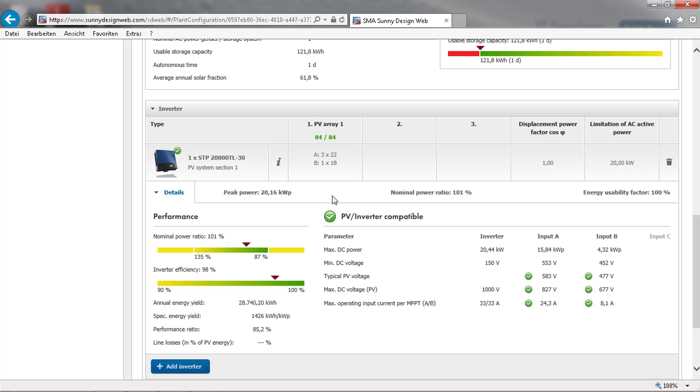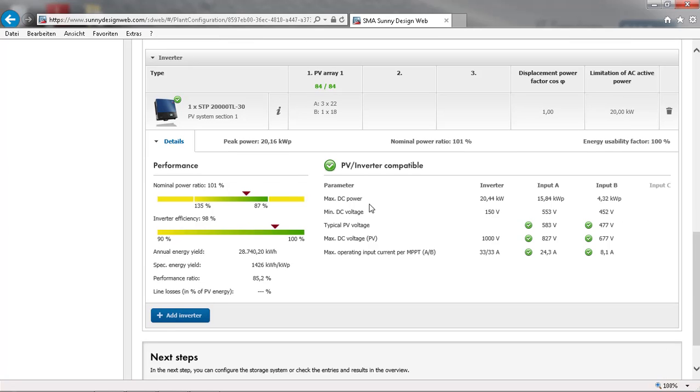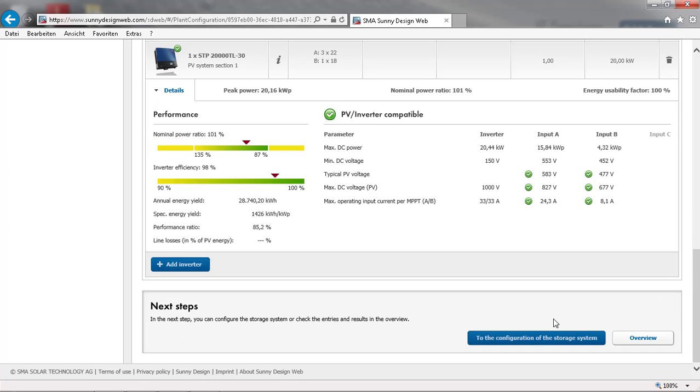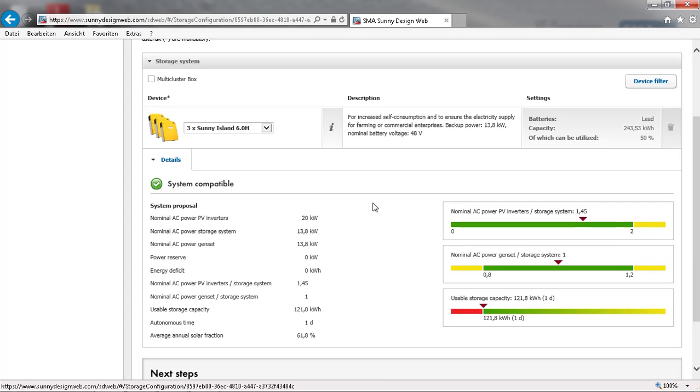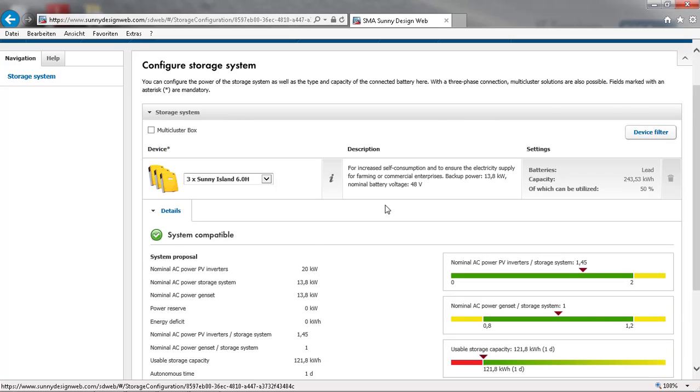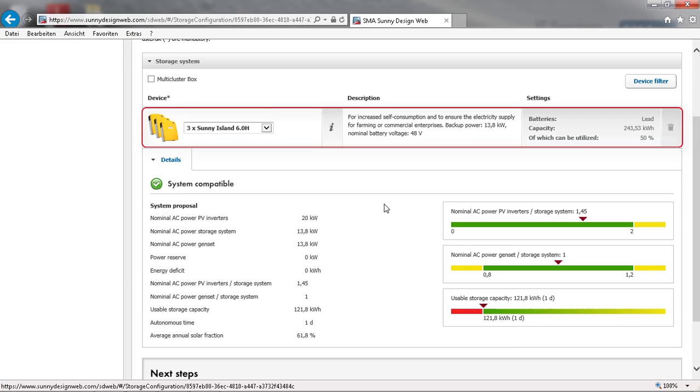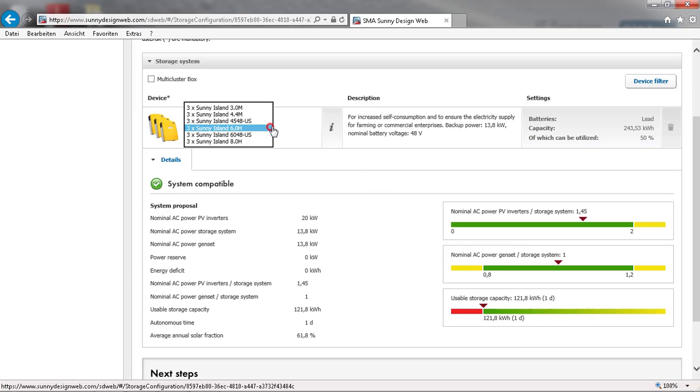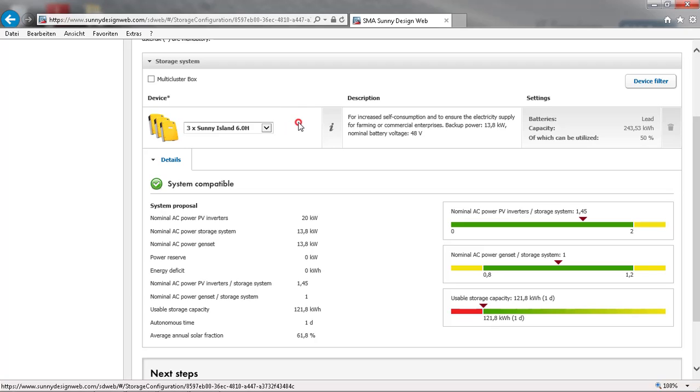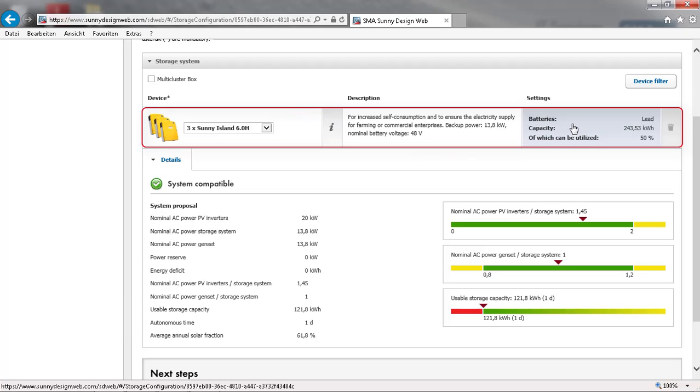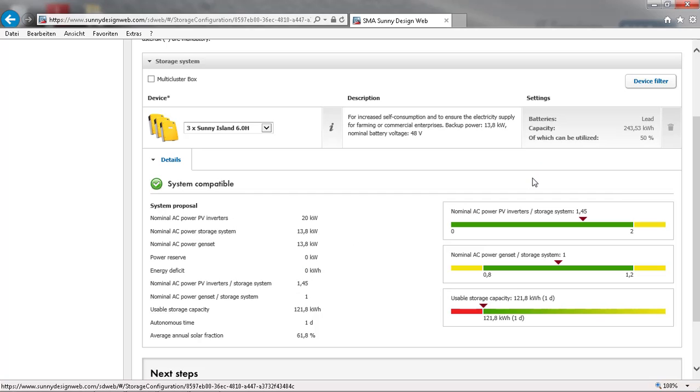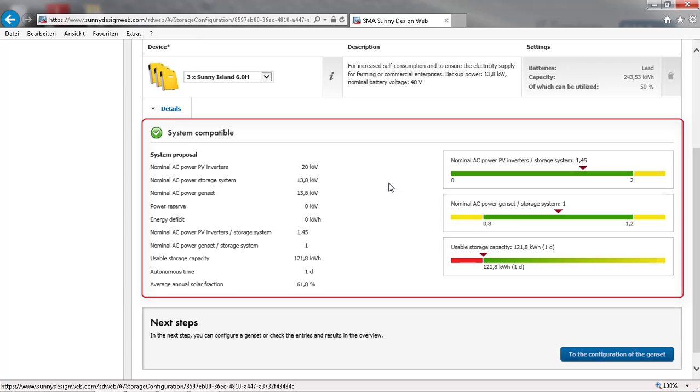Our next step is to continue with the configuration of the storage system. Here you can select the Sunny Island model or adjust the battery size and type. When making changes, please check that the system stability is not jeopardized by making sure the battery size is appropriate.